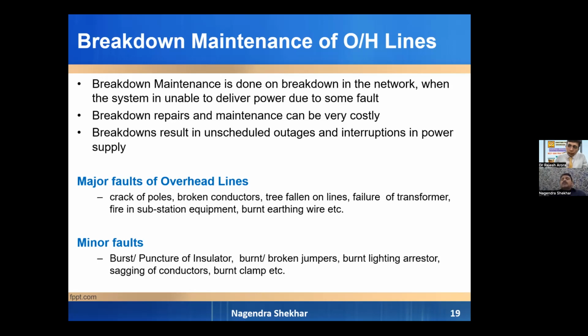Sometimes at night during peak hours, conductors are broken or our lines catch fire. That is a problem. These breakdowns result in unscheduled outages, interruptions in power supply, and annoyed consumers, which also brings down our performance. Higher outages lower the performance. Major faults in overhead lines are cracks in poles, broken conductors, trees fallen on lines, failure of transformers, fire in a substation, or even accidents. It has been noticed in Delhi that every day 2 to 3 vehicles hit our poles and break them. We have to replace them. These are the breakdowns. Minor faults are insulator punctures, fuse blown, broken jumpers, burnt lightning arresters, and sagging of conductors. These take less time to restore power supply.